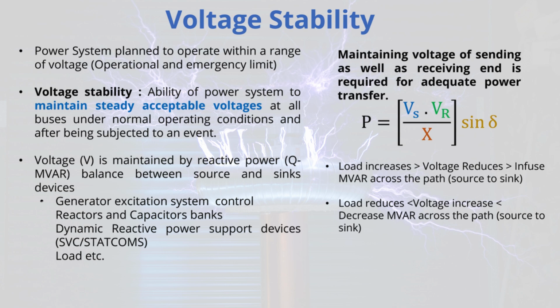and keep voltages up. The presentation connects this back to the power transfer equation too, saying maintaining Vs and VR is needed for power transfer. So voltage affects power flow angle too. Definitely. Lower voltage reduces Pmax, meaning you need higher angles to transfer the same power, which impacts rotor angle stability. The material shows the typical scenario. Increased load, voltage tends to drop. To counter it, you need to infuse MVAR, add reactive support.